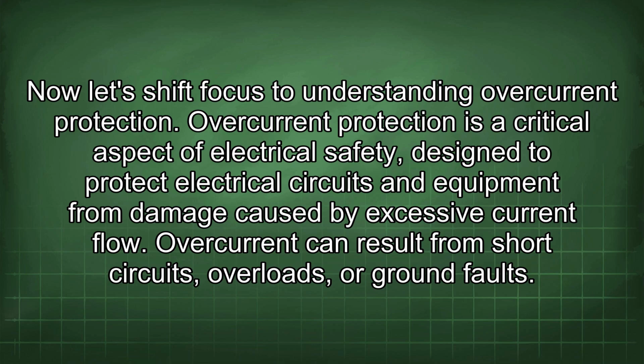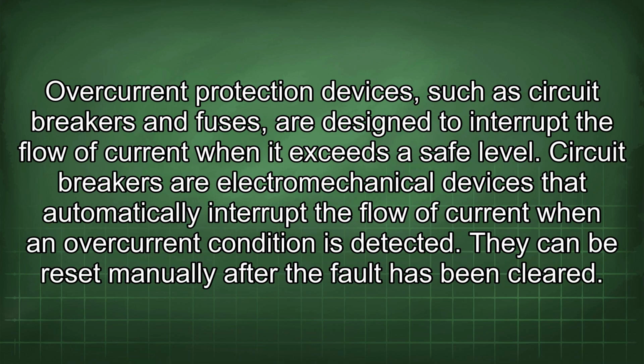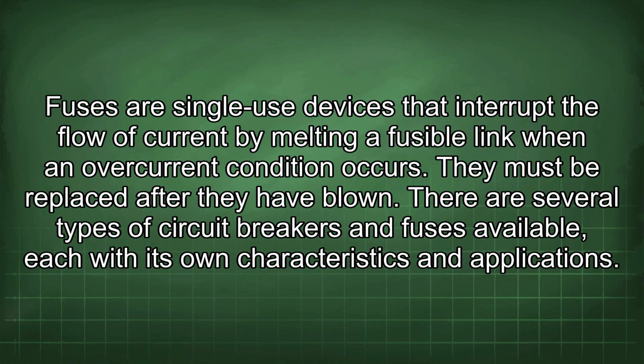Overcurrent protection is a critical aspect of electrical safety, designed to protect electrical circuits and equipment from damage caused by excessive current flow. Overcurrent can result from short circuits, overloads, or ground faults. Overcurrent protection devices, such as circuit breakers and fuses, are designed to interrupt the flow of current when it exceeds a safe level. Circuit breakers are electromechanical devices that automatically interrupt the flow of current when an overcurrent condition is detected. They can be reset manually after the fault has been cleared. Fuses are single-use devices that interrupt the flow of current by melting a fusible link when an overcurrent condition occurs.